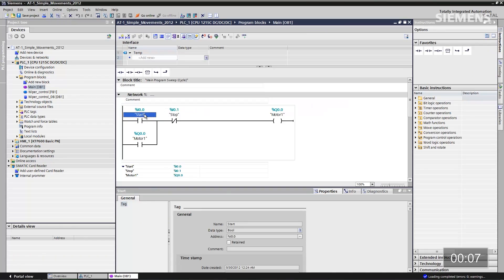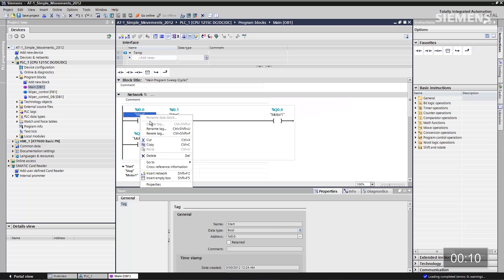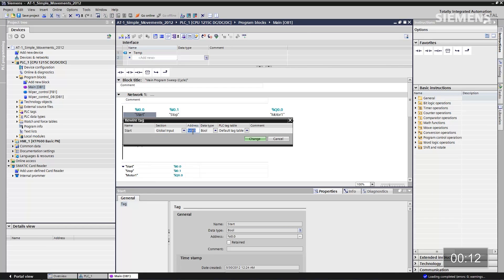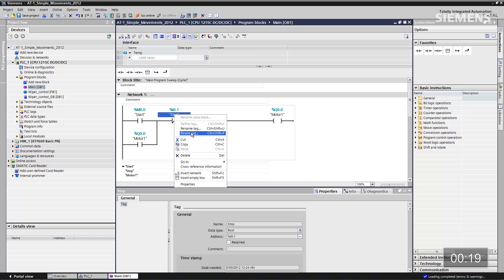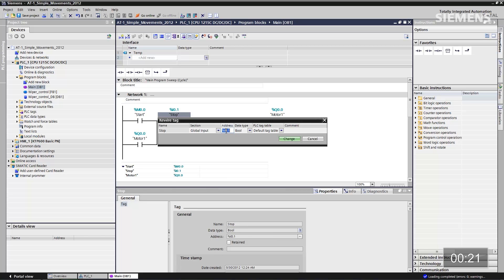Here's the project for this automation system we want to enable this app for. The first step is to go to the main OB — we want to use these two different tags: start and stop. Go to the start tag and click on rewire tag, change it to a global memory, and click on change. Then go to the stop tag, rewire tag, change it to global memory as well, and click on change.